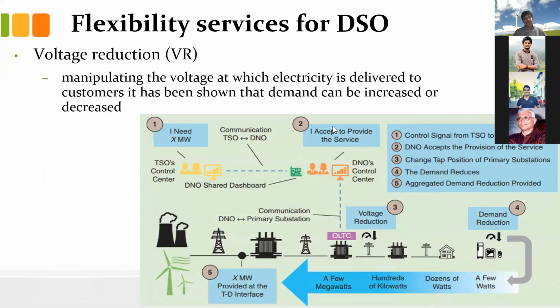I'll skip this. Okay, maybe it's the last slide. So now in the UK, they also use a technique called conservative voltage reduction. Remember, when you reduce the voltage towards the lower statutory limit, if it is a resistive load, the power output is V squared over R. So if you reduce the V, the power consumed by the resistive loads also reduces. So that is used in the UK to support frequency events. So these are some of the issues and some of the solutions.